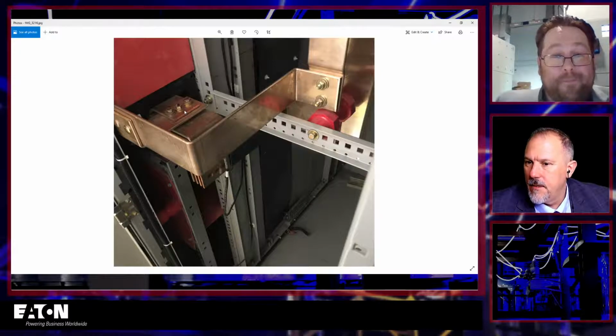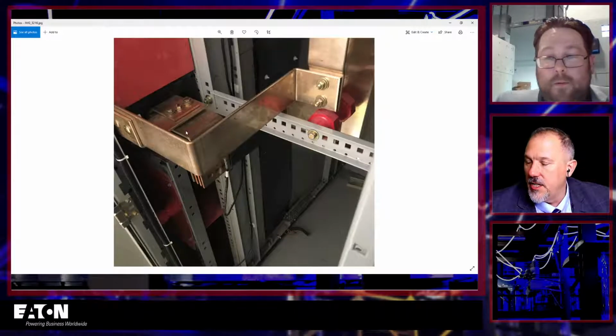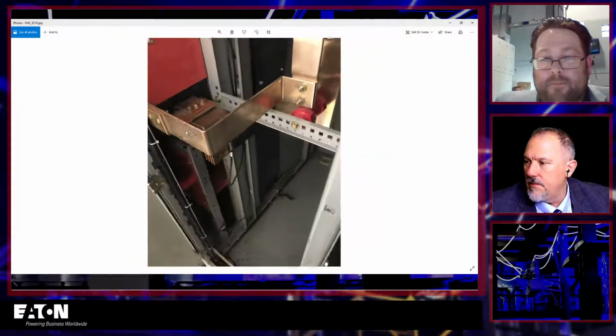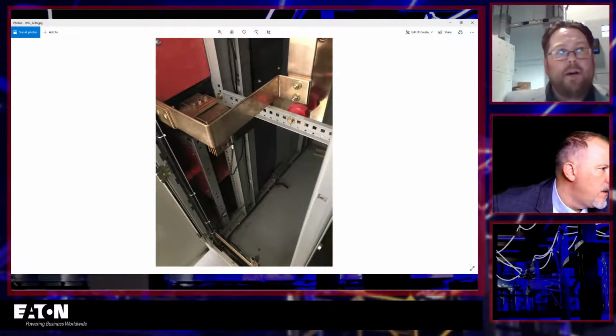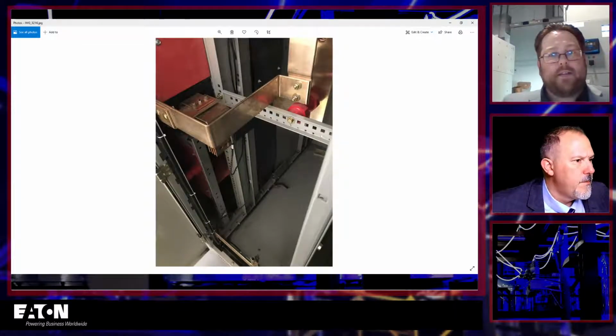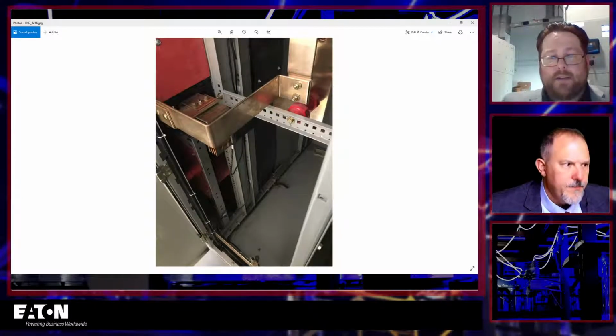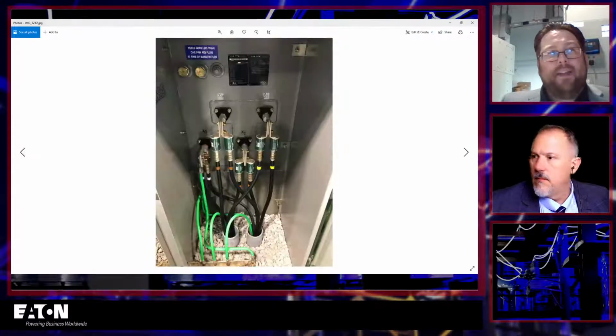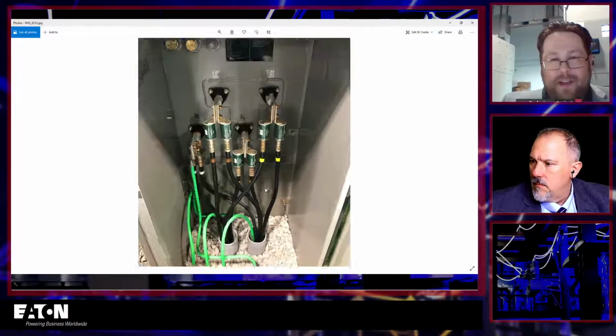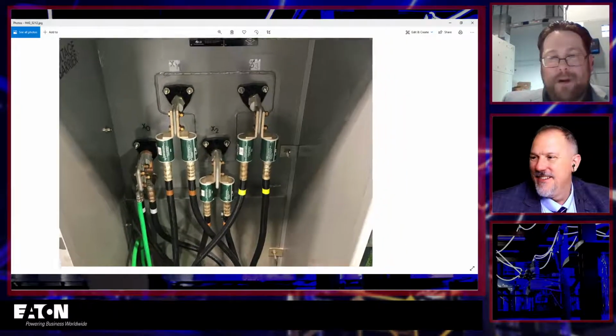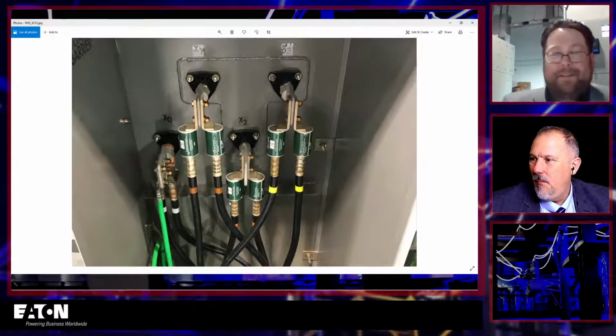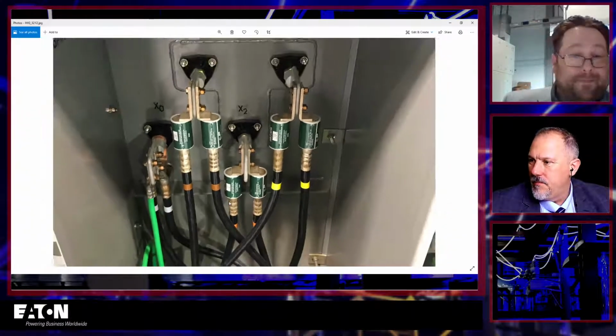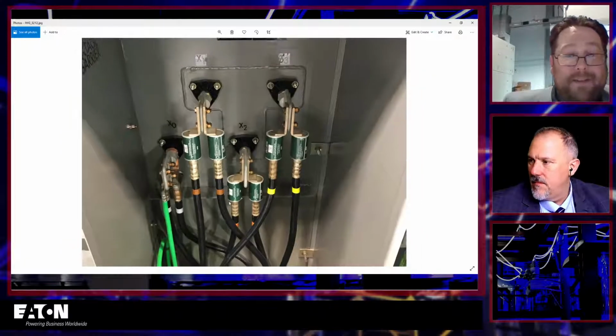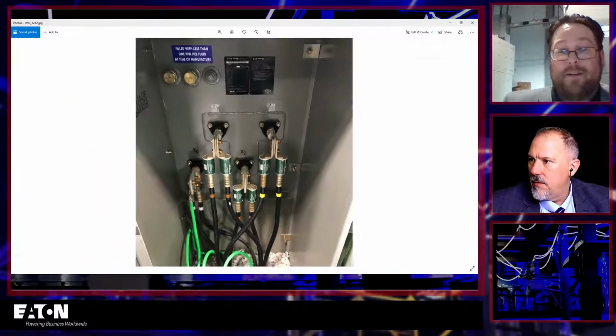Oh, Tamaki says there's a code requirement about phase arrangement. There very well may be, Tamaki. I know there are manufacturing standards, ANSI standards around that. I think though it uses that word typical here and there, so there are times when we flip them ultimately. So what you're looking at here, Tom, is actually a pad mounted transformer.